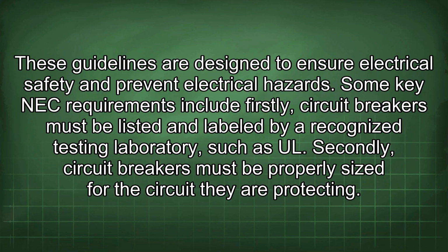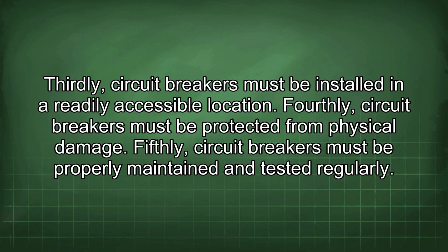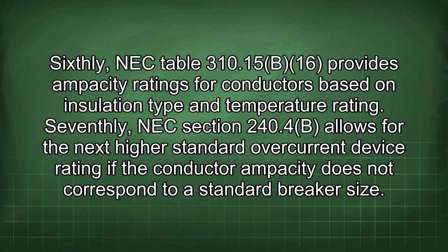UL. Secondly, circuit breakers must be properly sized for the circuit they are protecting. Thirdly, circuit breakers must be installed in a readily accessible location. Fourthly, circuit breakers must be protected from physical damage. Fifthly, circuit breakers must be properly maintained and tested regularly. Sixthly, NEC Table 310.15(B)(16) provides ampacity ratings for conductors based on insulation type and temperature rating.